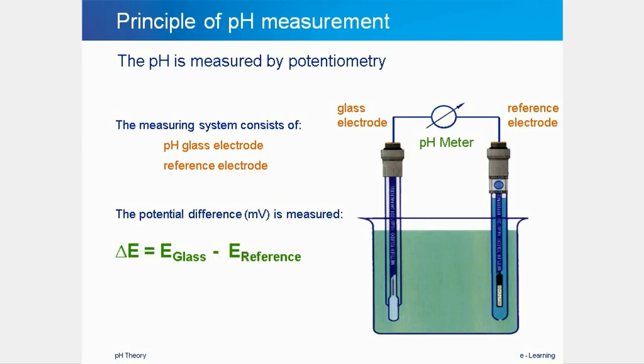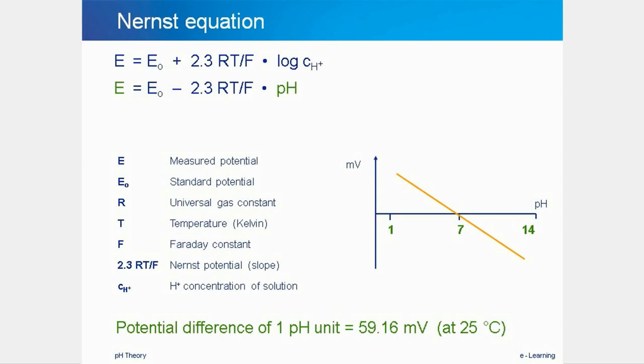The principle of pH measurement is that one takes a sensor with a glass membrane which is sensitive to hydrogen ions, and that this sensor therefore shows a certain reaction to the sample solution. To use this reaction quantitatively, a second sensor is needed — the so-called reference sensor or reference electrode. This electrode is not responsive to the sample solution and has a constant potential against which the measurement sensor potential changes depending on the amount of hydrogen ions. The potential between the two electrodes is therefore a measure for the amount of hydrogen ions in the solution and thus for the pH value.